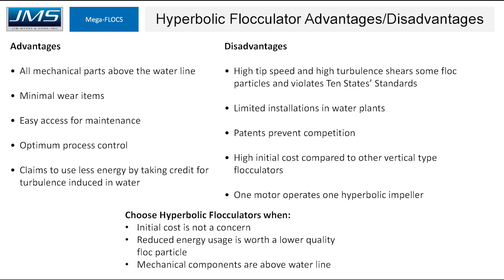Disadvantages of hyperbolic flocculators are that the high tip speed shears some floc particles, and they typically violate Ten State Standards, running at 6 to 9 feet per second on the tip. There are limited installations in water plants, some patents prevent competition, and there is a high initial cost compared to other vertical type mixers. One motor operates one impeller, adding to cost. You might choose this if initial cost is not a concern, reduced energy usage is valued, and all mechanical components need to be above the water level.